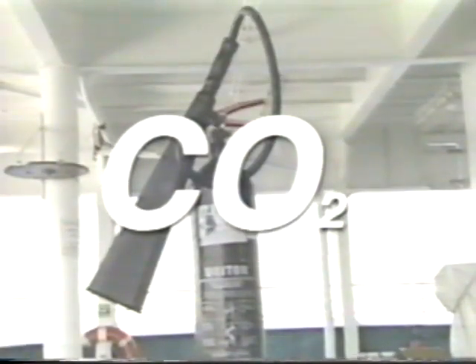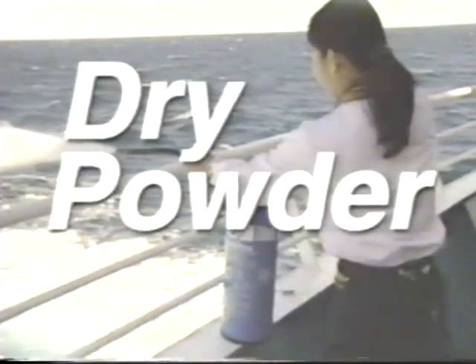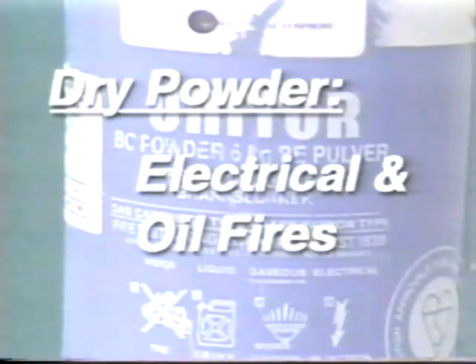Okay, fine. Thank you. Here's a brief recap of the fire extinguishers used on board. The CO2 extinguisher, painted black, is used for electrical fires. The red extinguisher is water and can be used on wood, carpet, sheets, and towels. The foam extinguisher, painted cream, can be used on wood, carpet, sheets, towels, and oil fires. And the dry powder extinguisher, painted blue, is best for electrical and oil fires.